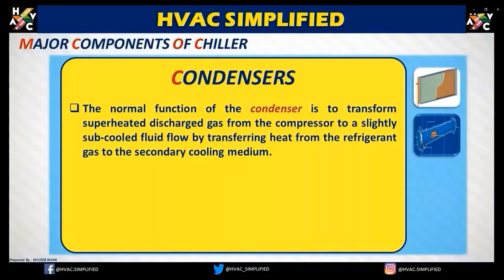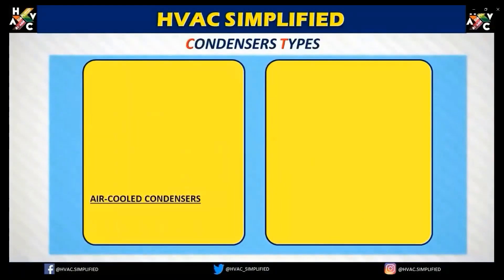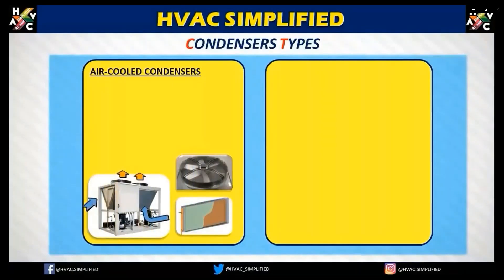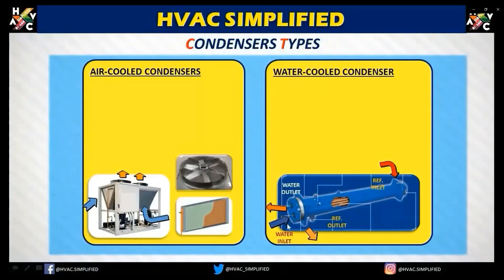The most common secondary cooling media are air and water. In an air-cooled condenser, air is passed through and discharged from the top via an axial fan. In a water-cooled condenser, the refrigerant passes through a shell and tube heat exchanger, and water acts as the medium to transfer the heat.